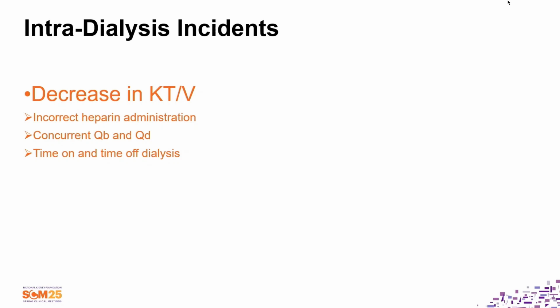Because when is time supposed to start? Not when the blood reaches the dialyzer. It's when you achieve the prescribed blood flow. That's the time start for your calculation. And from the moment you put your patient on to when you achieve the prescribed blood flow could be 5 minutes, depending on what's happening with that patient. Is 5 minutes critical in your calculations for Kt/V? Yeah, it can be. If you're looking for 1.2, which CMS requires, and you're at 1.18, that 5 minutes could actually give you that 0.02 difference.